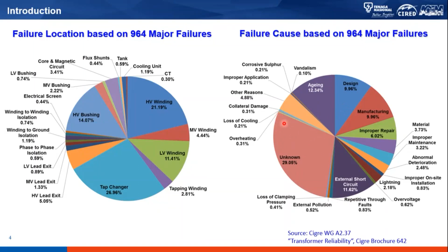Looking at the location of failure based on 964 major failures, on the left you can see the tap changer, HV winding, and LV winding are the major locations of failure, not to mention the bushings. On the cause of failure chart on the right, aging and design are factors, but unfortunately there's a high number of unknown cases too. This needs further investigation so we know what types of failure actually cause transformers to fail.